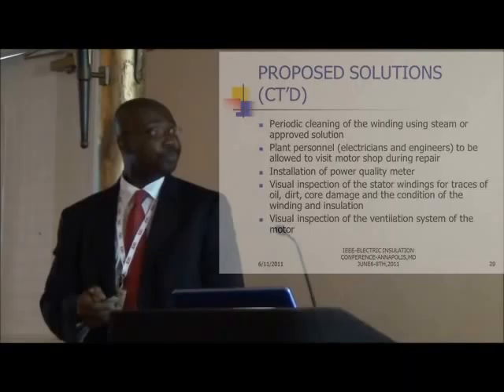We developed a preventive maintenance program for the craft to clean the windings, change the filters, and clean the ventilation systems when motors come offline. Another finding was that both electricians and engineers were not following up when motors were sent to the shop — they were only communicating remotely. We proposed that electricians and engineers physically go to the motor shop to provide oversight over the repair, winding, and impregnation processes.